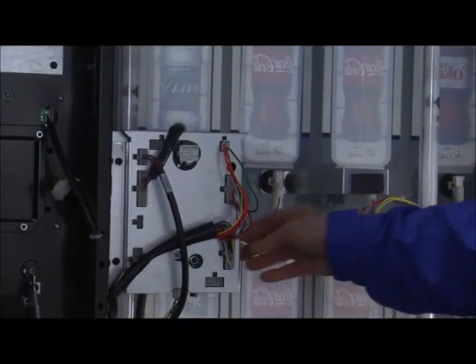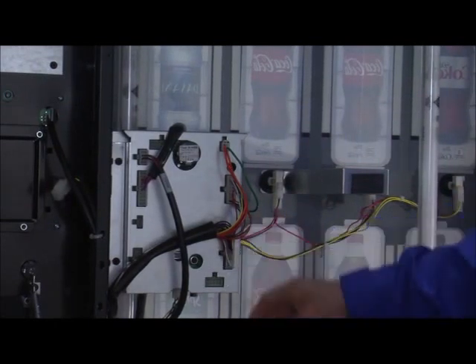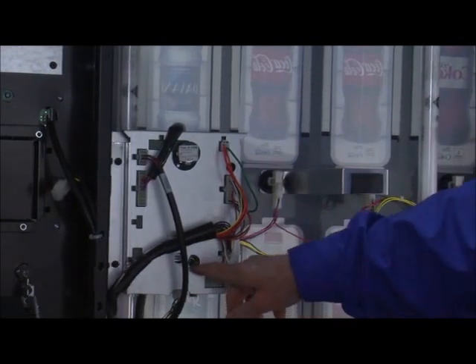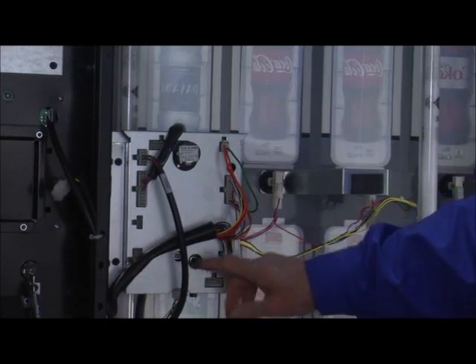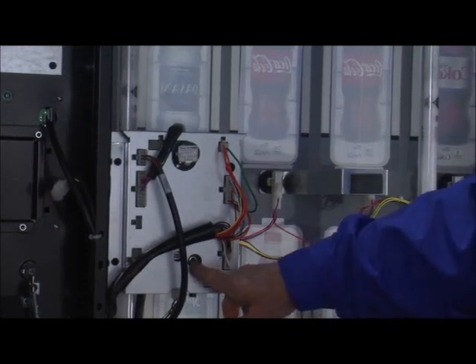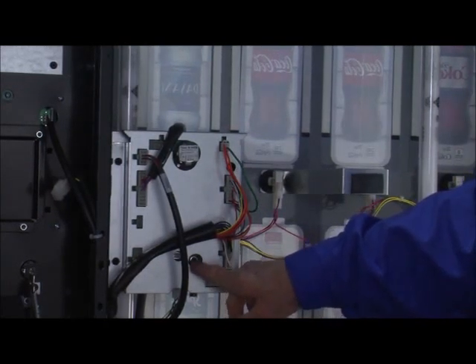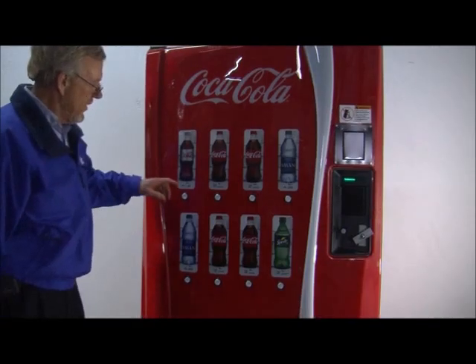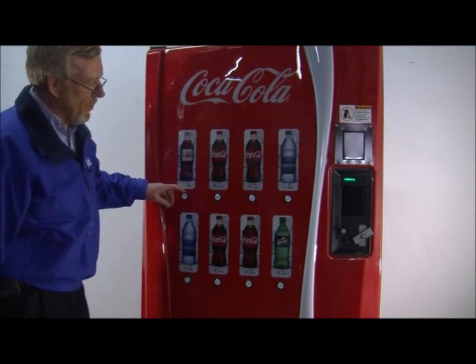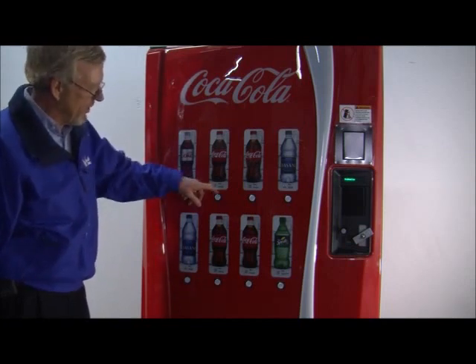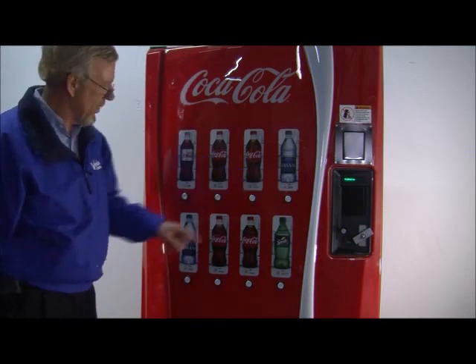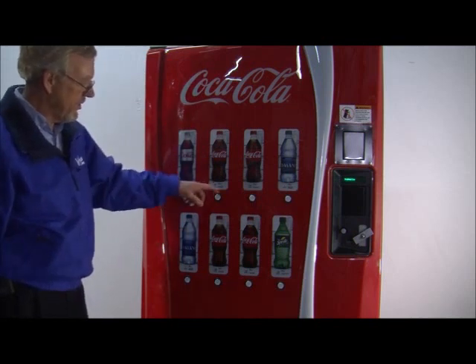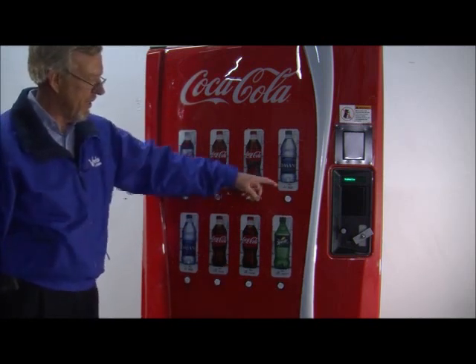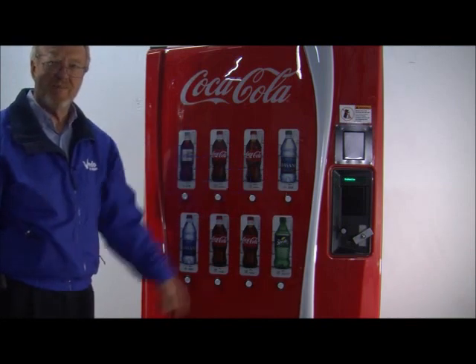To enter programming on the 12.6 control board, there's a mode button located in the lower portion of the control board. By pressing the mode button 1 time, diagnostics will appear in the LED readout on the front of the machine. On the front of the machine, we're using 4-button programming. Button 1, button 2, button 3, and button 4. 1 is escape, 2 scrolls you up, 3 scrolls you down, 4 is the enter and save button.